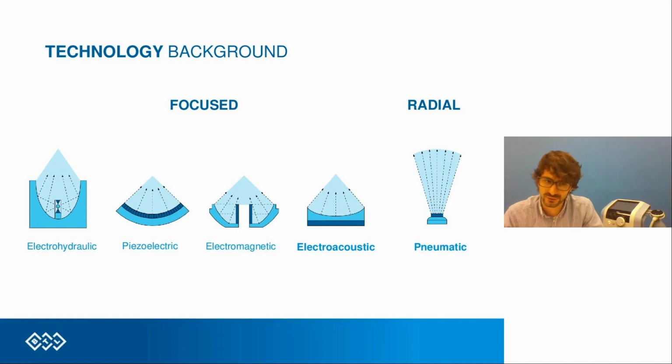But since you have hundreds of them on these devices, each of them is producing a small shockwave. And by concentrating these shockwaves, they create a much stronger wave. Why I said that it's very opposite from the electrohydraulic is that with piezoelectric devices, the lifespan of these applicators is much higher. We are talking about a few million shocks that can be applied before the necessity of servicing or maintenance or changing the applicator.